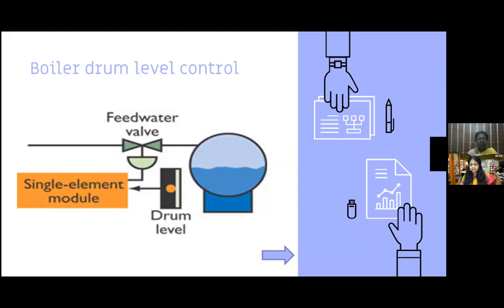So I find the difference, and the difference is applied as input to the controller. Here the single element module consists of a controller. Based on the algorithm available, the controller calculates something and gives me a signal. The signal is used to operate a control valve, shown here as the feed water valve. The valve is a pneumatic control valve operated using a pressure signal as input, so I need to convert my signal into a pressure signal and then apply it to the valve.